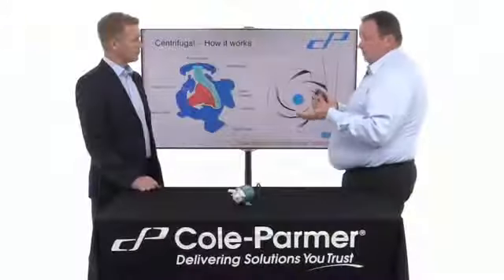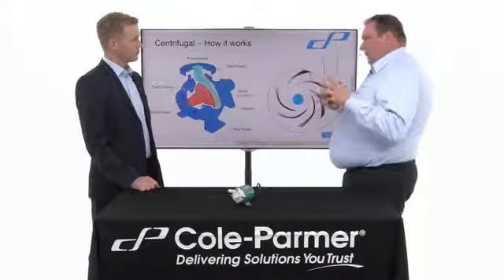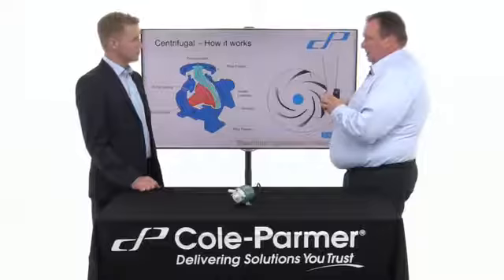So one of our other videos, if you haven't seen it, we actually talk about systems and system conditions. We need to make sure that the suction conditions, so the conditions before the pump, are such that there is enough liquid to keep flowing into the pump. Otherwise, what they do with centrifugal pumps is they'll put the pump in the water. You get submersible versions. You get solids handling versions. They're used on sewage works. But you have to still have that liquid to go into the pump when it starts up.